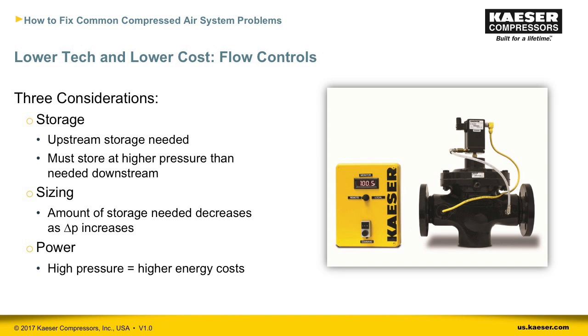If you're interested in a flow controller, think about these three considerations. First, you'll need storage before the flow controller, and it must be stored at a higher pressure than what's needed downstream at the point of use. Second, the size or amount of storage will depend on the pressure differential. Less storage is needed as the pressure differential increases. Third, it requires more power and higher energy costs, the higher the storage pressure is. Every 2 psi increase is an additional 1% in power consumption.